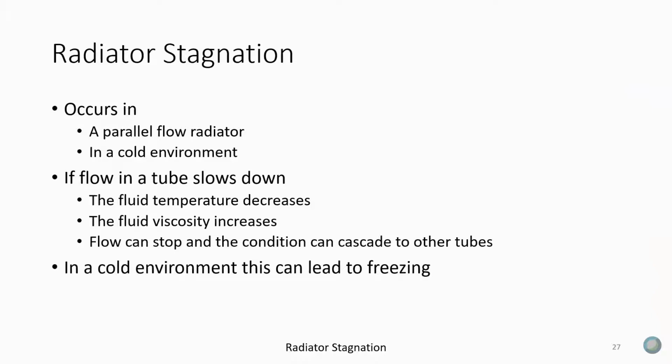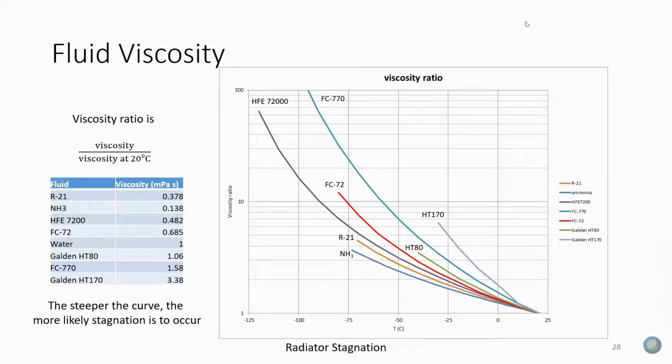They had modeling that we would think of as rudimentary, but was sufficient to allow them to try to figure out what was going on in the radiator. But it was really, really hard, and they had a difficult time with it. So, generally, and then of course, as I said, once we go to water propylene glycol, stagnation's bad because it leads to freezing. It doesn't just slow the stuff down. And so now you've got a host of other issues. How do you thaw this thing and such? So stagnation is probably not a good thing to go for as your first design.